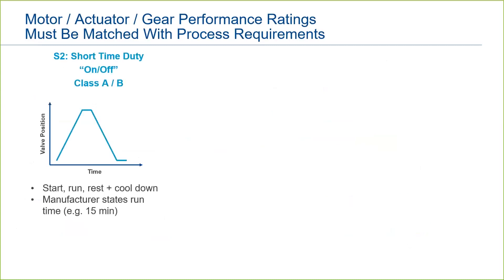There are three basic types of motor and actuator ratings, dictated by the performance of the motor, actuator, and any external gears. The first is S2 short-time duty. This may also be called on-off duty, or class A or class B, depending on where you are in the world. All these terms mean basically the same thing, which is a situation where the motor starts, runs, stops, and cools down.